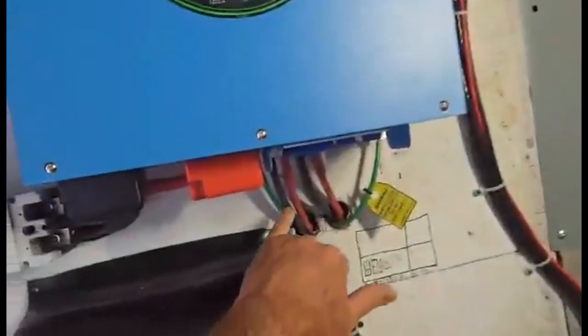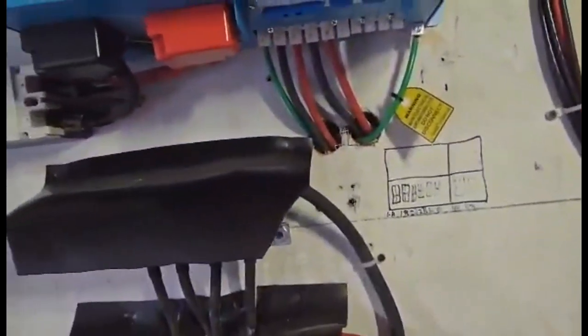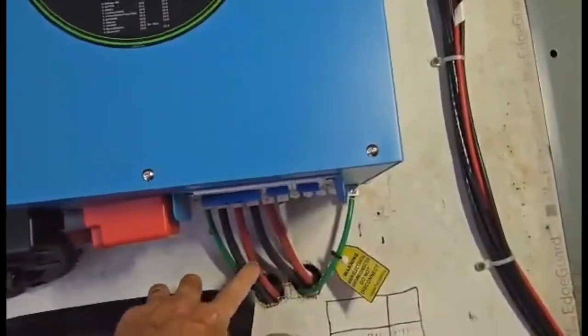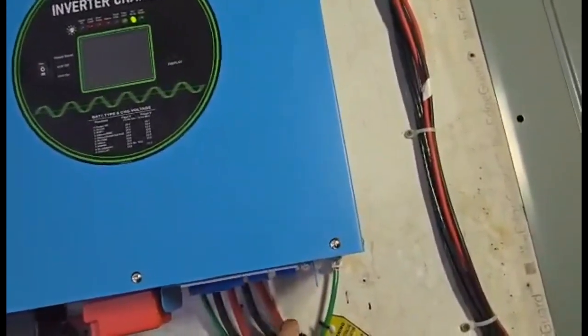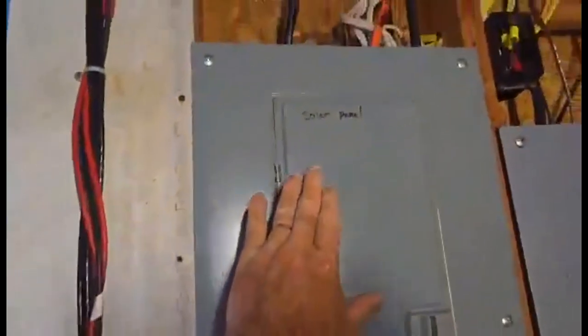The way it works is you have 240 volts coming in — 110 and 110 coming in from your commercial panel. You have a ground hooked to a ground rod and your two hots. You do not bring a neutral into this. This produces your neutral outgoing. So you have your outgoing connections here: 110, 110, your neutral, and a chassis ground. Those wires are going over to my subpanel.